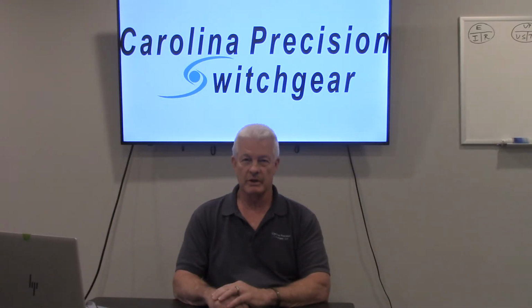The first thing you want to do is to find out why the circuit breaker tripped. You do not want to just close the breaker back in because you might be closing it in on another fault. So if it has a solid state overcurrent device, or some of them have the analog but they'll have a little push button, a lot of times it will tell you whether that circuit breaker tripped on long time, short time, instantaneous, or ground fault. So find out first why the breaker tripped before you close it back in.